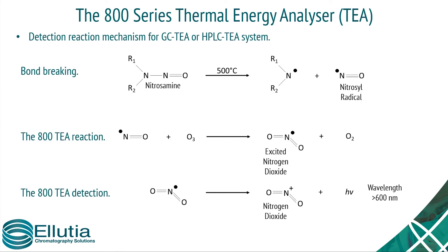This is the generic reaction — the equations for the reactions for the TEA system. The nitrosamine is heated, which releases the nitrosyl radical, which then enters the TEA where it is reacted with ozone to form an excited state of nitrogen dioxide. When the nitrogen dioxide relaxes, it releases a photon of light, and that is what is detected by the TEA.